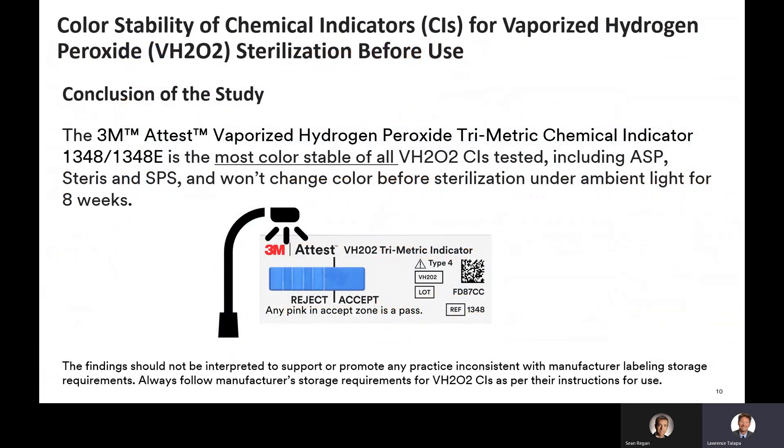This study is the basis for 3M's claim that the 3M Attest vaporized hydrogen peroxide trimetric chemical indicator 1348/1348E is the most color stable of all chemical indicators tested — including ASP and SPS — and won't change color before sterilization under ambient light for up to 8 weeks. I also want to remind everyone that the findings should not be interpreted to support or promote any practice inconsistent with manufacturers' labeled storage requirements. Always follow manufacturer storage requirements for vaporized hydrogen peroxide CIs as per their instructions for use.